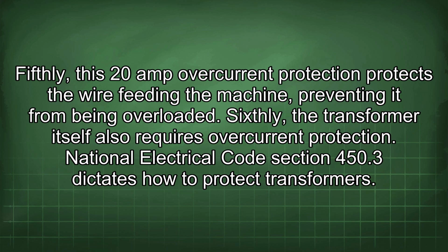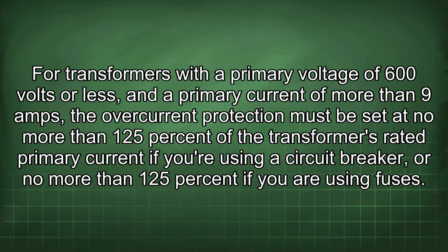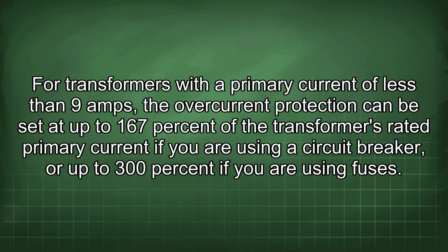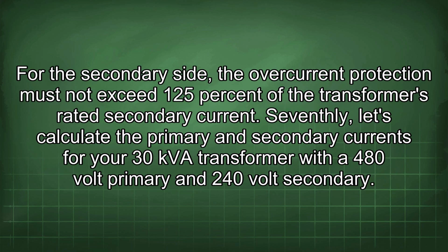National Electrical Code Section 450.3 dictates how to protect transformers. For transformers with a primary voltage of 600 volts or less and a primary current of more than 9 amps, the overcurrent protection must be set at no more than 125% of the transformer's rated primary current if you're using a circuit breaker, or no more than 125% if you are using fuses. For transformers with a primary current of less than 9 amps, the overcurrent protection can be set at up to 167% of the transformer's rated primary current if you are using a circuit breaker, or up to 300% if you are using fuses. For the secondary side, the overcurrent protection must not exceed 125% of the transformer's rated secondary current.